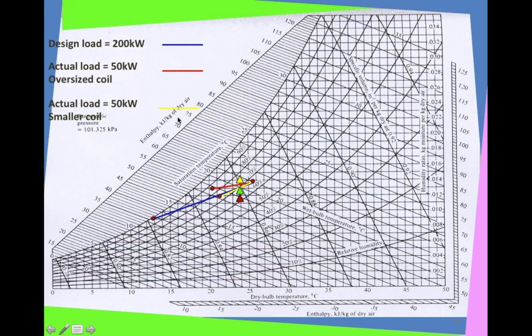I don't see that load anyway. My actual load is 50 kilowatts now at a part load condition. It's very, very humid because you see you hardly get any dehumidification here. And then if I change that to a smaller coil, I come down to my yellow performance. So I'm going to show you a very simple movement of the space condition. If I have the red line performance, actual load 50 kilowatts, large coil, this is where my space is going to be. It's going to be at the yellow condition here, which is very humid. If I change the coil to a smaller coil, it comes down to the green.